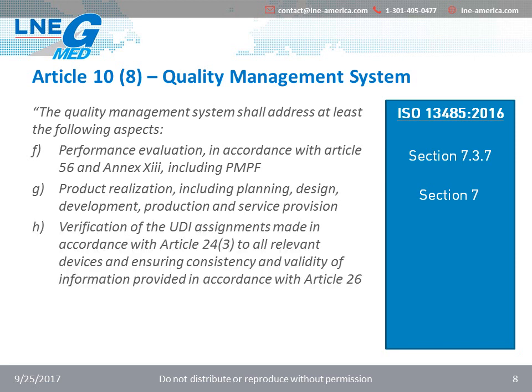The UDI. The UDI is a new requirement of the regulation. We see that it has to be done in accordance with Article 24, and the validity of information provided in accordance with Article 26. Even if it's a new requirement of the regulation, it finds its correlation in Section 7.5.8 of the ISO 13485:2016 version, which requires documented procedures for product identification. So here again, we have a requirement and we would have procedures in place to be sure that we provide the right product identification.